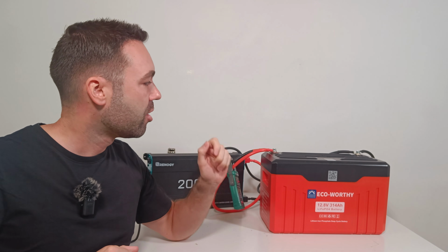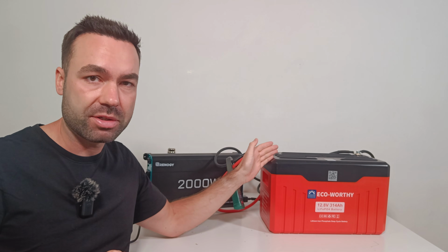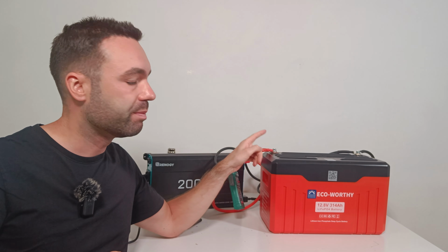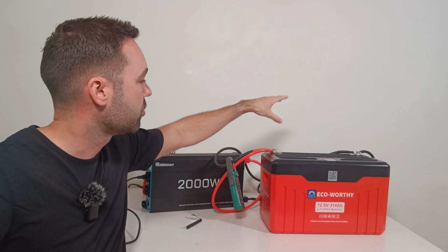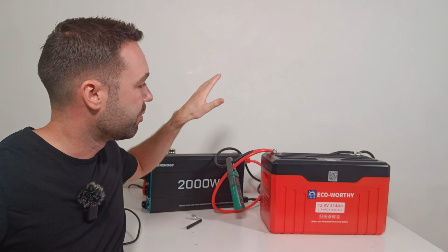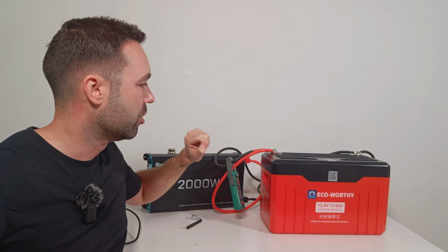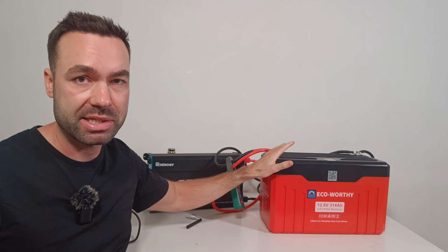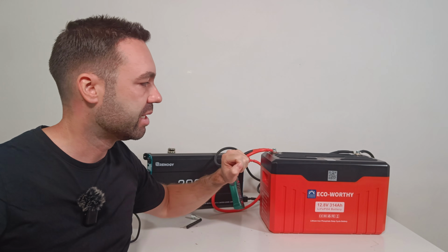So the next test will be to test the current carrying capacity of the BMS. I have two inverters here. I will apply a 200 amp load and see if the BMS can handle it for 15 minutes.